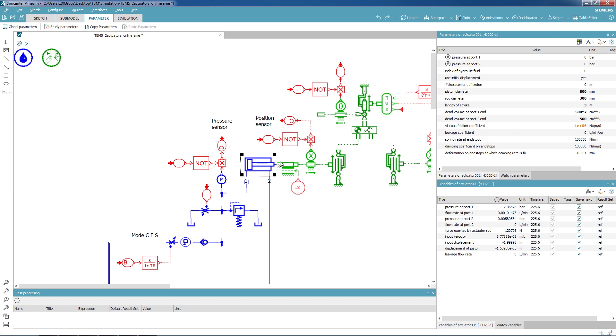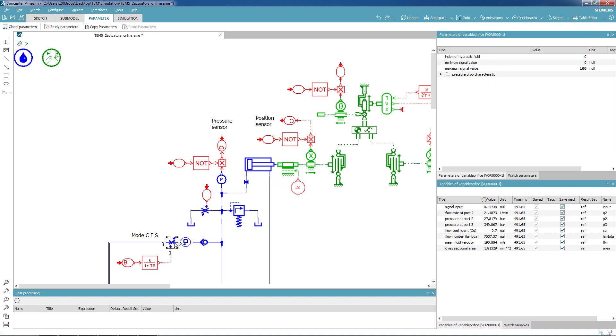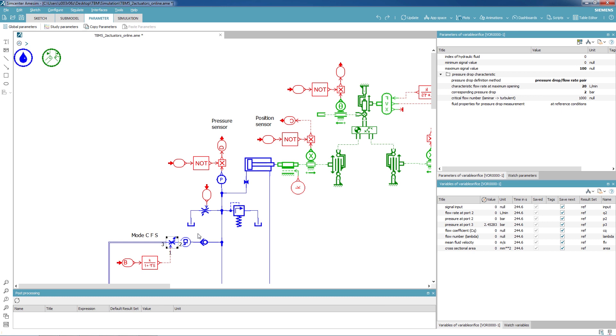We are controlling how fast this cylinder moves forward by regulating the flow that goes inside of it. This is done thanks to this regulating valve, which has been also parametrized with the pressure drop characteristics. This valve is receiving a command signal from the PLC.